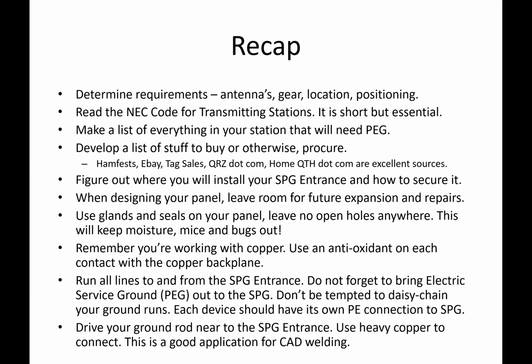If they're grounding via copper pipe entrance to your building and then bringing that over to your circuit breaker panel, you need to understand that you should bring that ground as it comes into your building on the copper pipe all the way out to your single point ground by its own separate conductor. You need to bypass any other connections there and understand that you're just trying to protect human life. You're trying to protect your gear as much as you can, but human life is where you need to live. You need to understand your own application so that you know how to proceed.